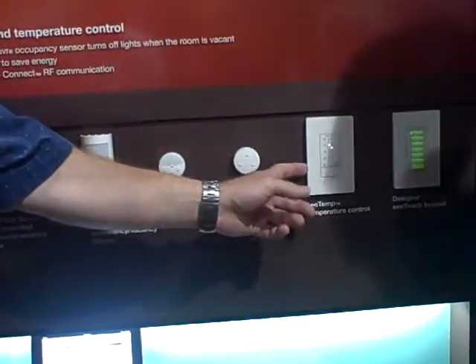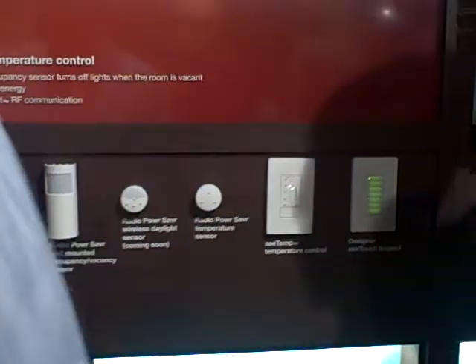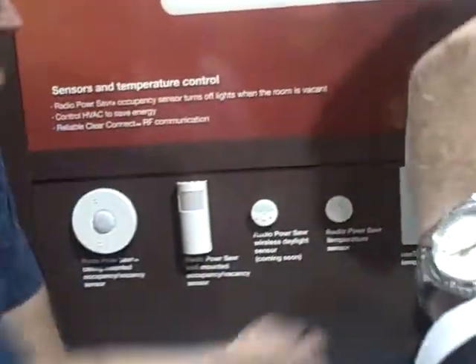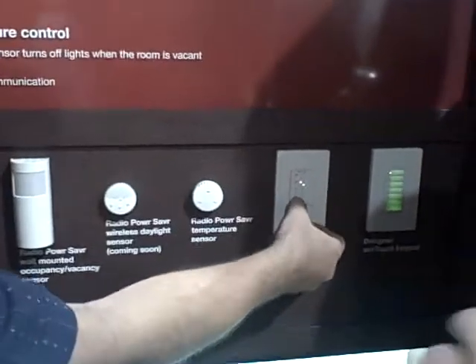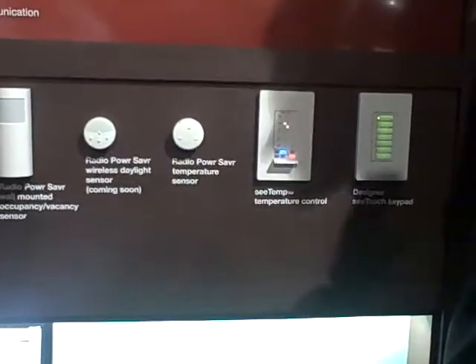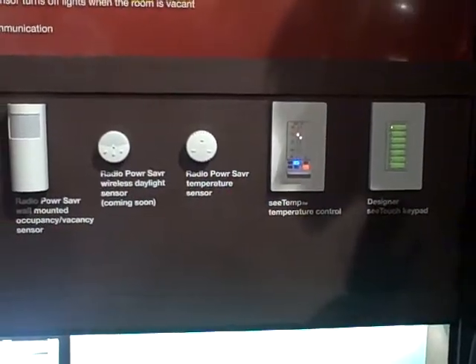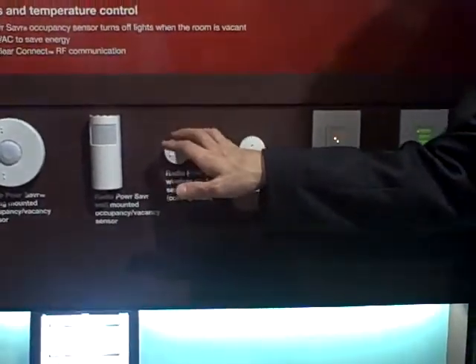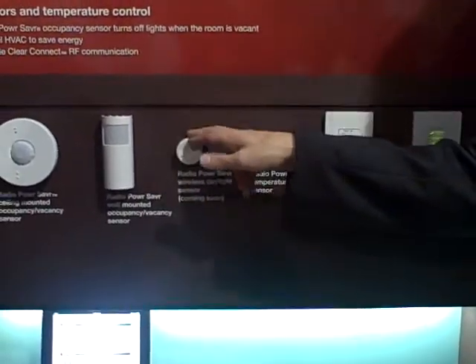In the past we interfaced with third-party daylight controls which just activated presets, but now this is really analog control. This thing can be set so there's variability in light level or shade position — it's a very powerful energy device. And we're very interested in feedback on this, as to what you might want to use a daylight sensor for residentially.